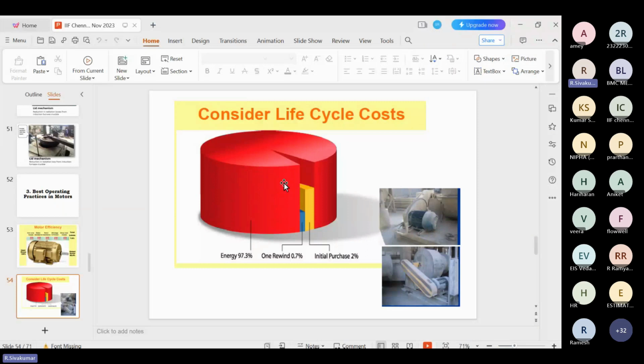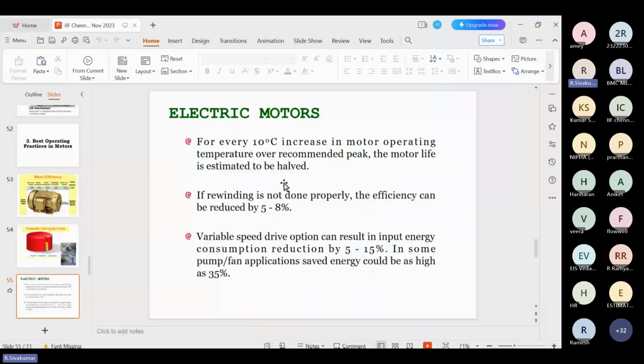For every 10 degree increase in an electric motor's operating temperature, the life of the motor is reduced to half. So the motor temperature should also be monitored. It is a good indicator. Nowadays, everyone has a thermal imager, or during COVID time we were using the IR infrared thermometer.